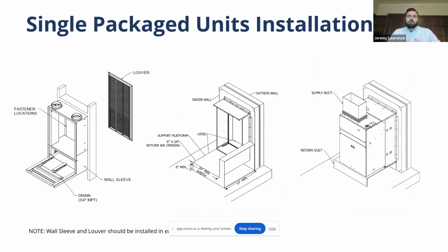So these units are installed into a sleeve, and the way this rolls through is, as the project is moving along, this space needs to be manufactured into the structure of the building, and then as the structure is going up, the sleeves are installed into the space by the general contractor usually, because they need to be fastened to the structure and then sealed. They don't require any insulation because of the way that they move. The fan operates through, provided that the return air is free to pull from around this unit. There's no worries about condensation or frost or air leakage.